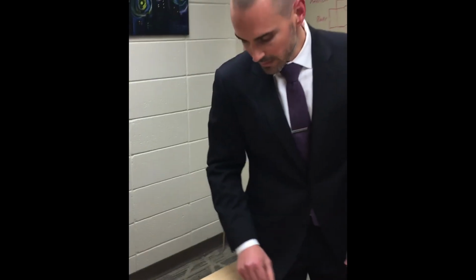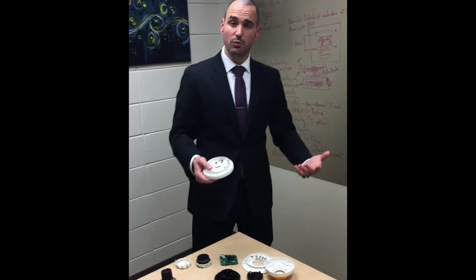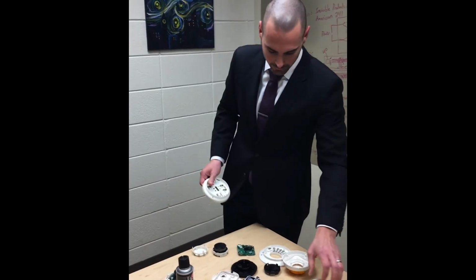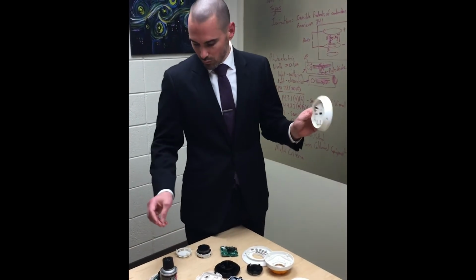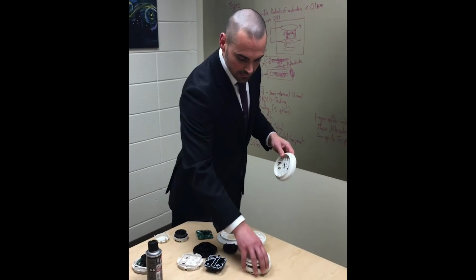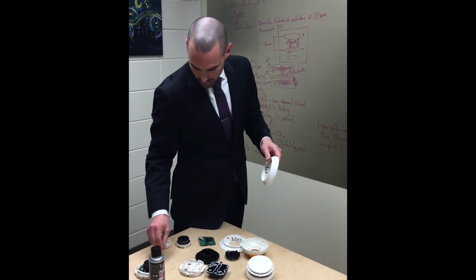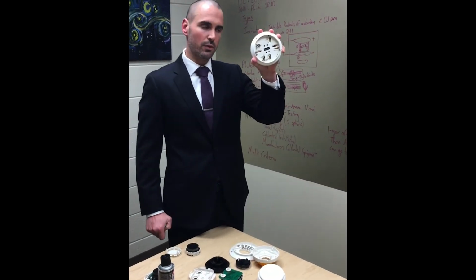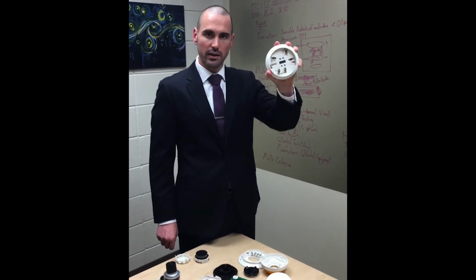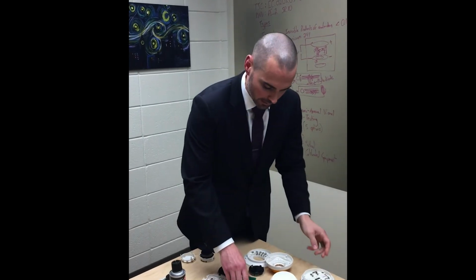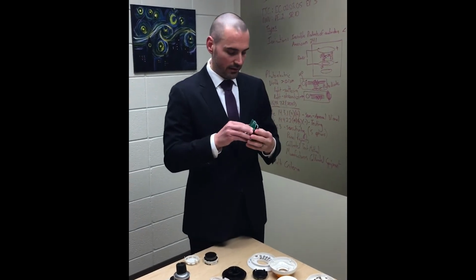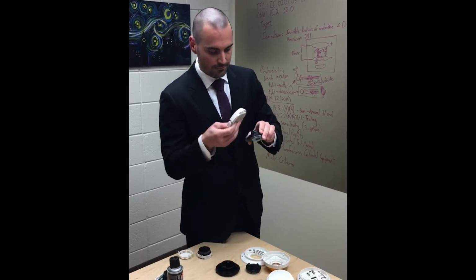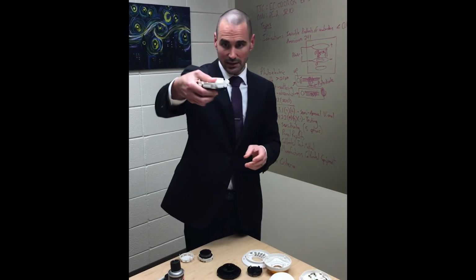I think it's also important to mention we have addressable detectors and non-addressable detectors, and all of these are addressable. We've talked about that in all of our videos. But one interesting fact is different detectors are structured differently. This base for Simplex is actually addressable, versus for Notifier, for example, the actual smoke head that goes in is addressable. The smoke head clearly all goes together, but that's what you see.